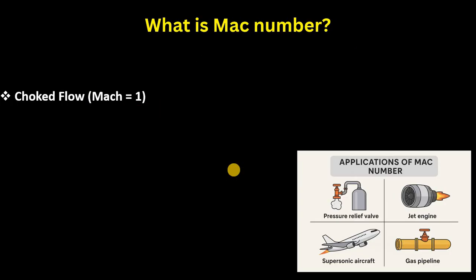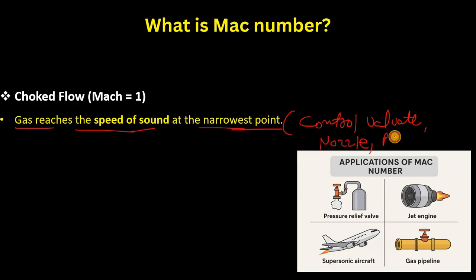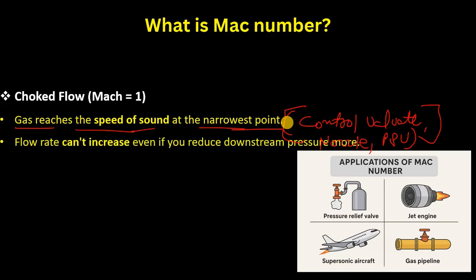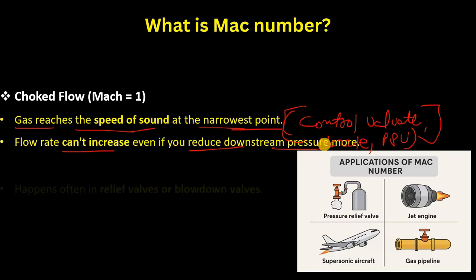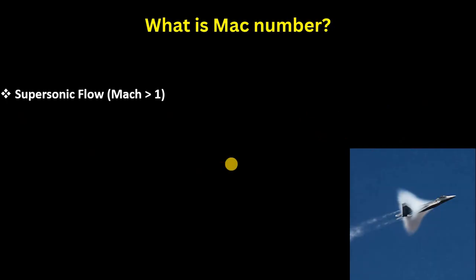When your Mach number is equal to one, choked flow occurs. The gas reaches the speed of sound at the narrowest point — such as a control valve or PSV nozzle. In that case, your flow rate cannot increase even if you reduce the downstream pressure further. This happens often in relief valves or blowdown valves.